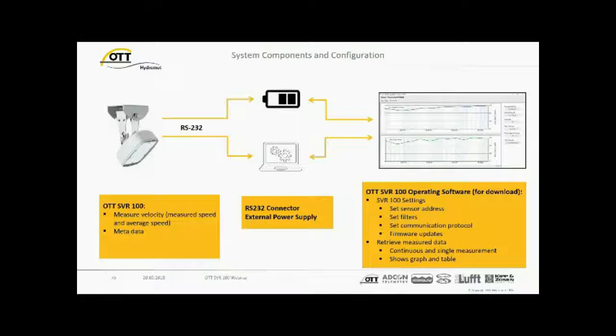And you will also be able to change the communication protocol between SDI12 over RS485 and Modbus RTU. But if your customer, you already know what type of communication is required in the field, then you can select the right order number, and we can distinguish between. And we have a factory preset communication protocol for you, so there's no need to take this software and to change it afterwards.